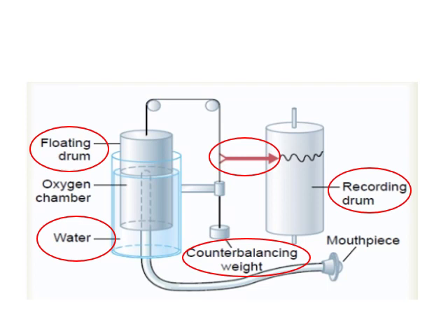In the chamber is a breathing gas, usually air or oxygen. A tube connects the mouth with the gas chamber. When the person breathes into the tube, air enters the chamber from the lungs and the drum rises and the pen is lowered. Thus, a downward deflection represents expiration, and an upward deflection represents inspiration. The recording is known as a spirogram, which measures the volume of air moved in and out of the lung.